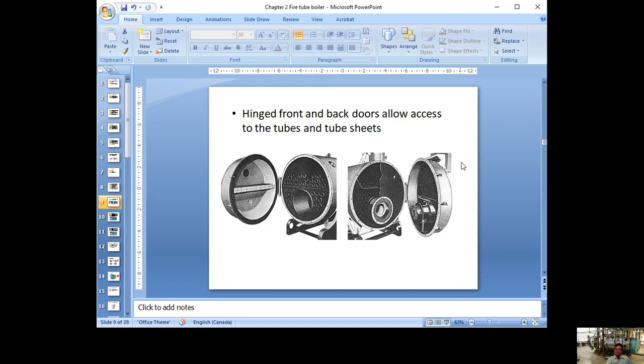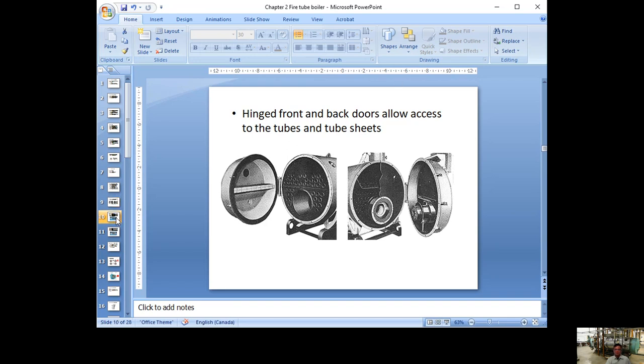Some of them even have a hinge to swing open. Notice the chimney is on the front — that means it's an even-pass boiler. When the fire goes to the other side and comes back, if the chimney is on the front, it's an even number of passes. If the chimney is at the back, it's an odd number of passes.